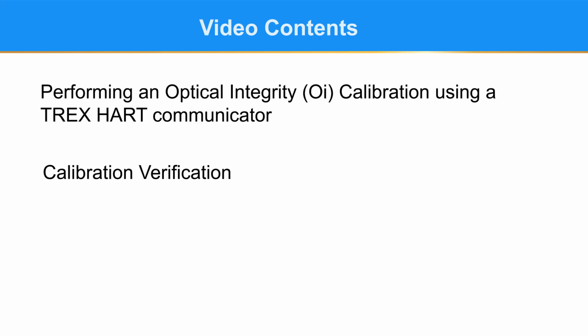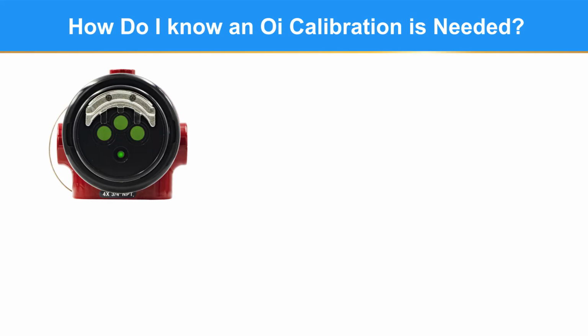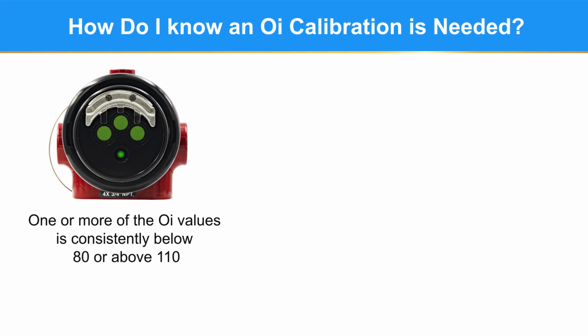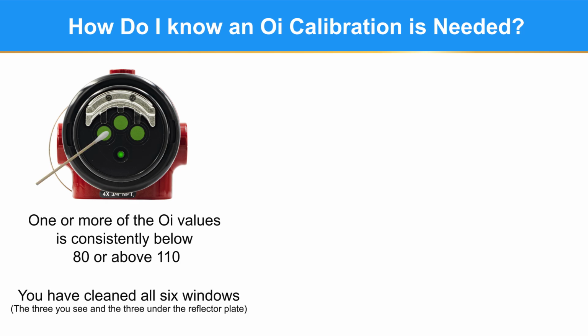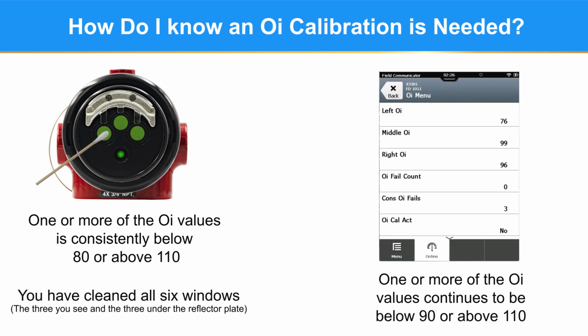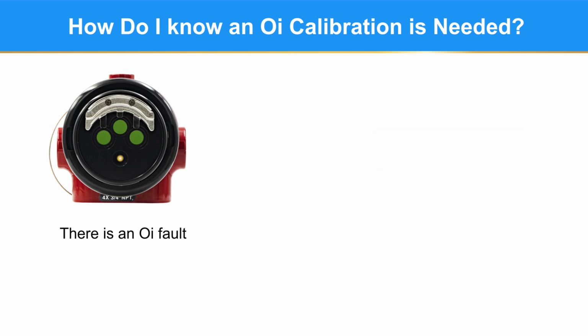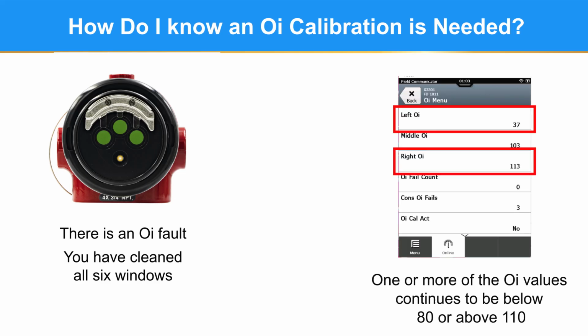Let's get started. An OI calibration is needed if one or more of the OI values is consistently below 80 or above 110, and you've cleaned all 6 windows and one or more of the OI values continues to be below 80 or above 110. Another scenario is that there is an OI fault. The status LED is yellow and you've cleaned all 6 windows and one or more of the OI values is less than 80 or greater than 110.